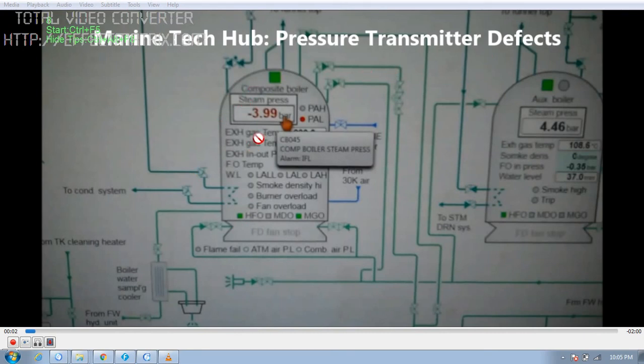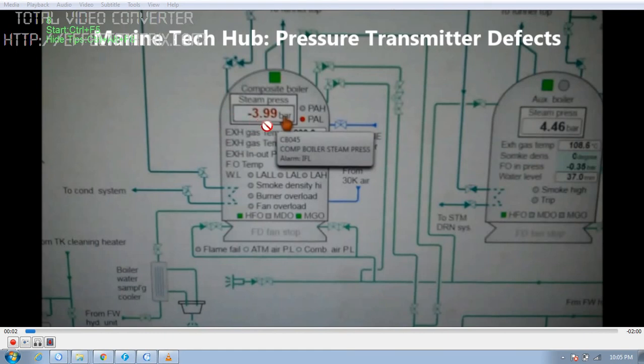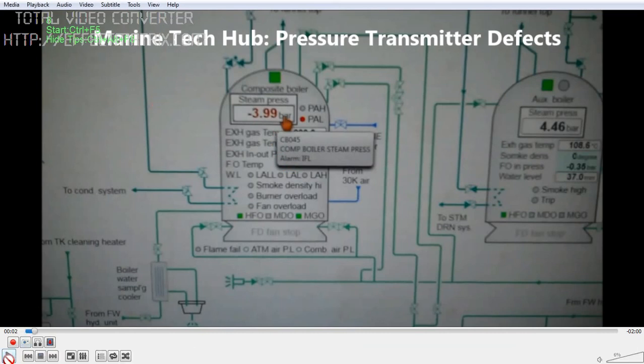Right now we get an alarm. We have a composite boiler and an exhaust gas boiler here. The ship is running and we have pressure in the composite boiler, but the computer is showing minus 3.99. It is showing a low pressure alarm, but actually the composite boiler has a pressure of 6 bar on the actual pressure gauge. I will be explaining how you are going to check the defects.